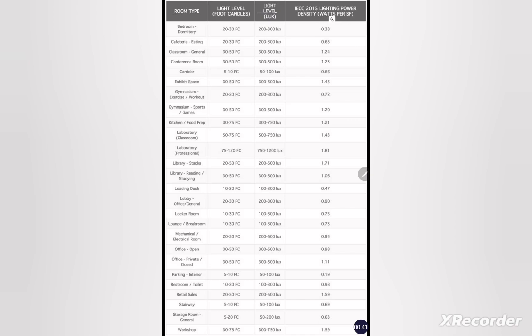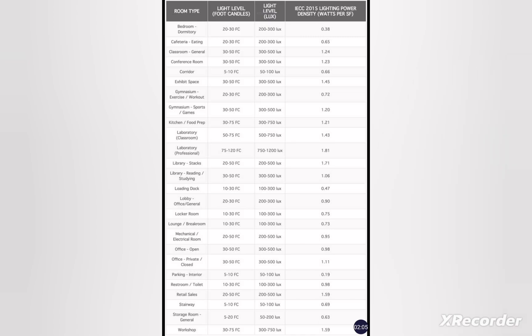The wattage requirement per square foot for a corridor is 0.66 watt, which we can convert to wattage per square meter. For every room there are different lux level requirements and different wattage per square meter requirements. For example, parking internal needs around 50–100 lux and 0.19 watt per square foot. A conference room needs 300 to 500 lux at 1.23 watt per square foot. A classroom also needs 300 to 500 lux at 1.24 watt per square foot. I will make a separate video on this topic. Based on this, I allotted 8 lights to satisfy the corridor requirement. I will provide a link in the description to a video where I discuss lighting design thoroughly.